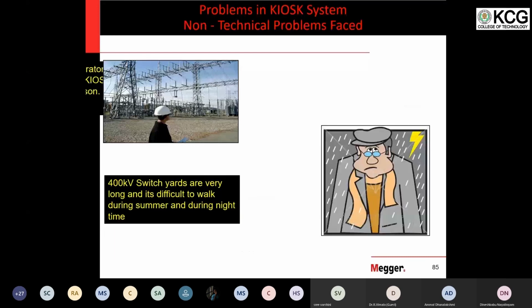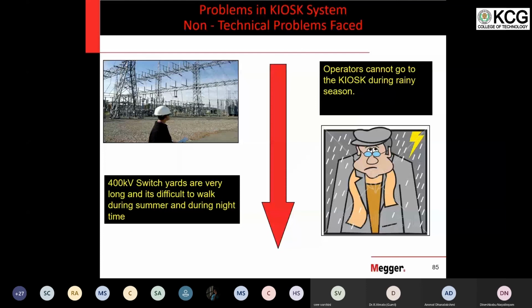So just see this 400 kV switchyard. Areas like northern India, especially, and nowadays why should we go only to North India? Even in our place, Chennai, you have a lot of hot seasons. Like, I think from March till June, it is very hot. So imagine the life of an operator. When the SCADA fails, he has to move from kiosk to kiosk because the operator has to write the hourly reading. Every 1 hour, he has to write the reading in a book. This is automated now. SCADA is actually writing everything. All the manual work is eliminated.